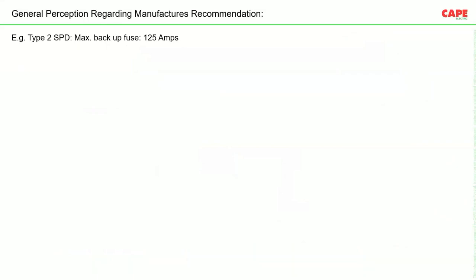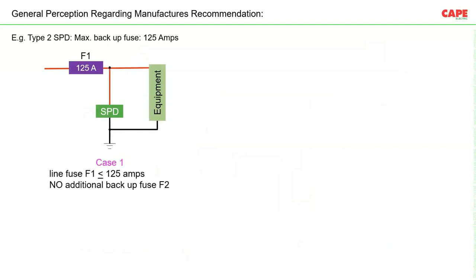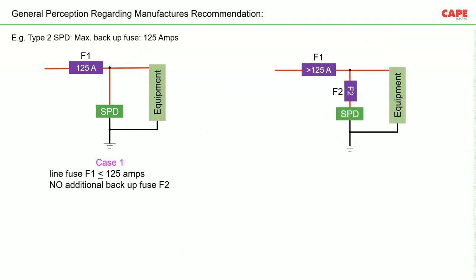Regarding general perception on backup fuse rating: every manufacturer specifies a maximum ampere rating for their SPD — for example, 125 A. If the main incomer fuse F1 is less than this specified value, no additional backup fuse is technically required. If F1 exceeds this value, an additional backup fuse F2 must be installed with a rating below the specified threshold.